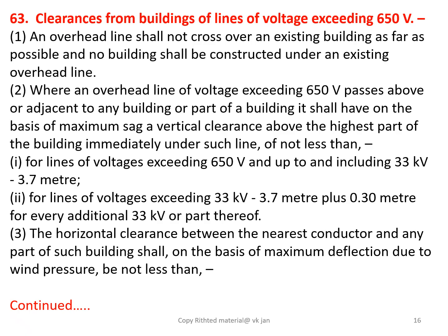Friends, now we are discussing Rule 63 of CEA Regulations 2023 that gives clearances from buildings of lines of voltage exceeding 650 volt. First, an overhead line shall not cross over an existing building as far as possible, and no building shall be constructed under an existing overhead line.